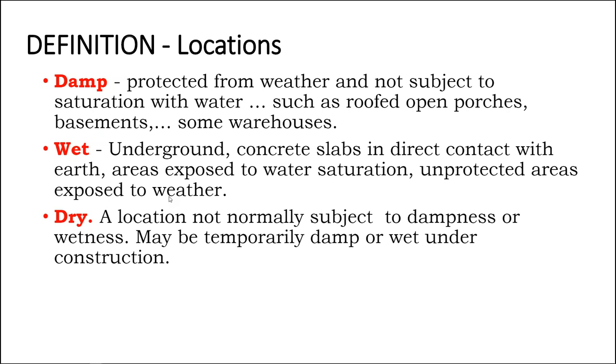And the reason for that discussion is you can get away with different kinds of material selection for a damp environment versus a wet environment. The cable that I like to use for my wire runs through the attic is actually rated for a damp environment. So I'll run that cable through the attic and stick it out the underside of the eave. Then I'll put a box underneath the eave and transition the wire in that box to something more appropriate for a wet environment.